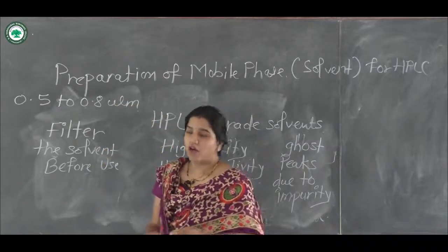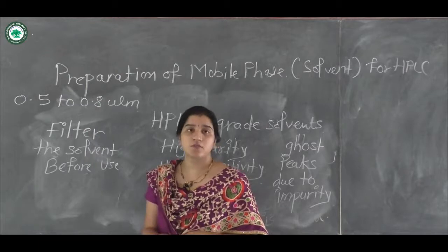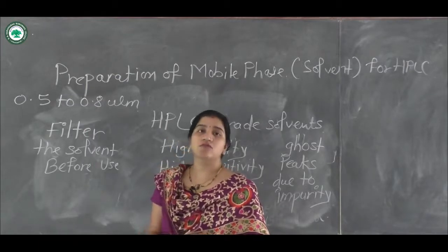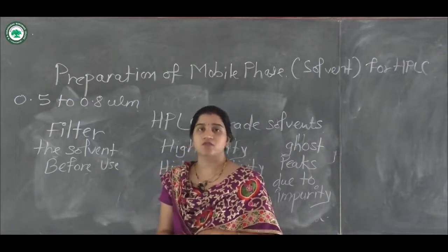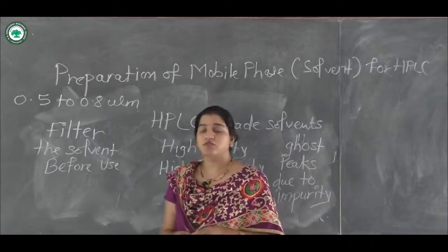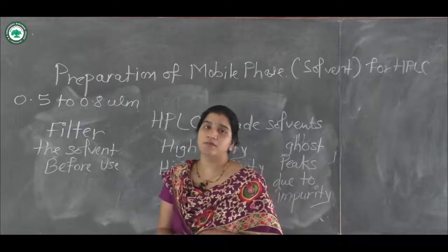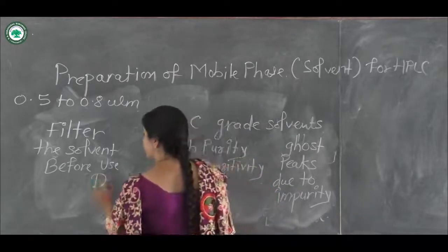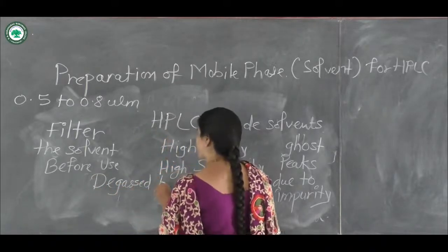So always prefer to use the HPLC grade solvent. If it is not possible and you are using another solvent, then always use the solvent from the original bottle, and if this is also not possible, then always filter the solvent through the filter before use. There should not be any impurity. Along with it, the solvent should be degassed before use.